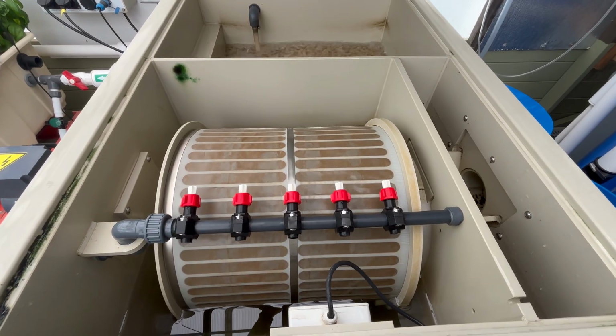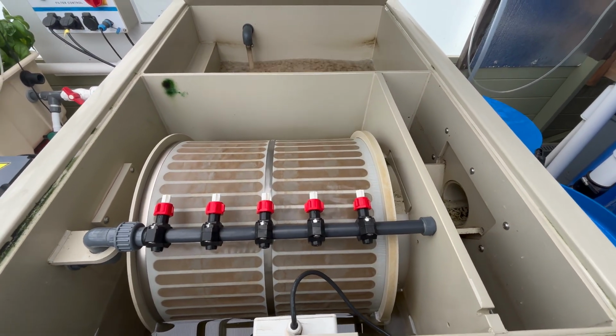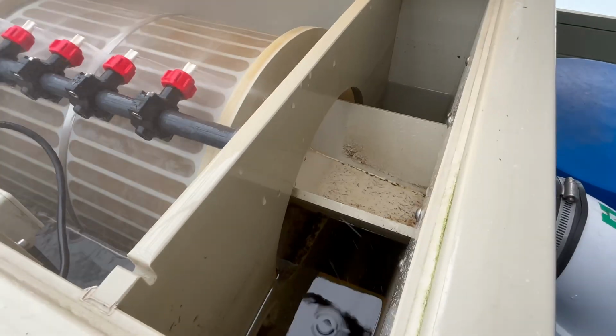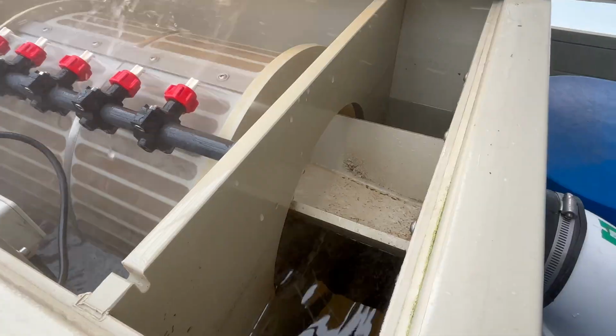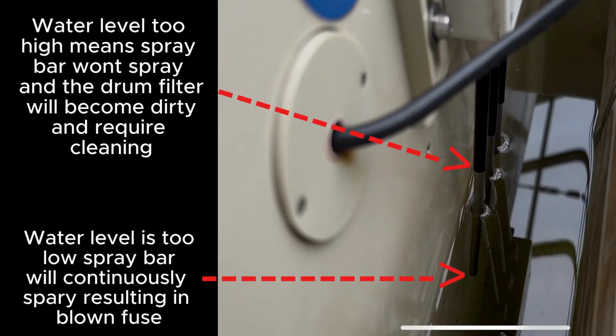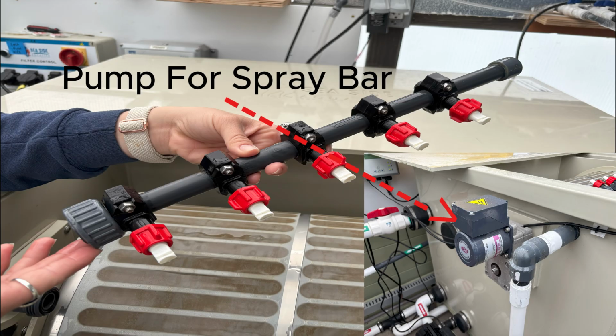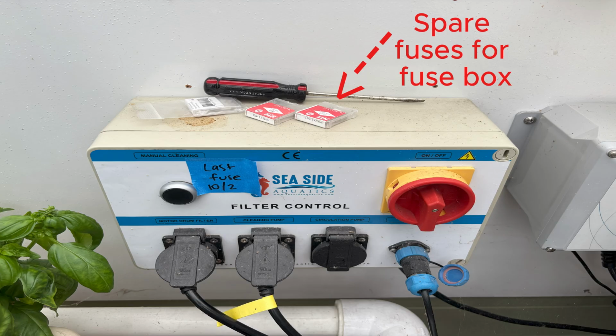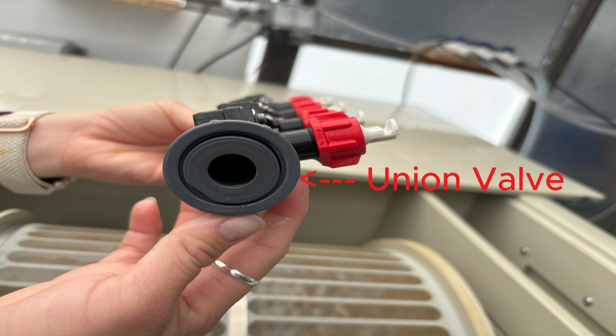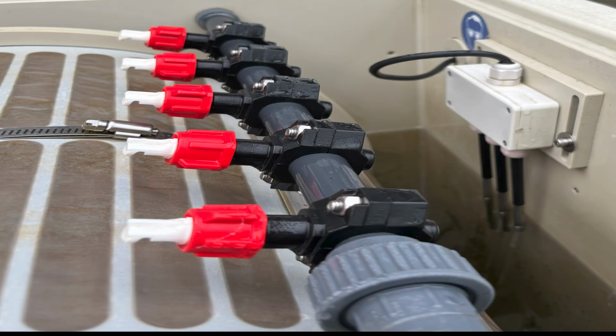Another issue that can occur is when, again, the water level is too low, and when the spray down occurs, the probe is covered but very minimally. Normally, from the top of the sensor to the bottom, it takes a short amount of time for the water level to drop. But if the water level is much lower on the sensor, it can change. This overworks the pump controlling the spray bar, which, if left unchecked, will blow a fuse and damage the pump. If this occurs, please notify a staff member or the professor immediately. More uncommon problems are damaged or clogged spray bars, which require removal and cleaning.